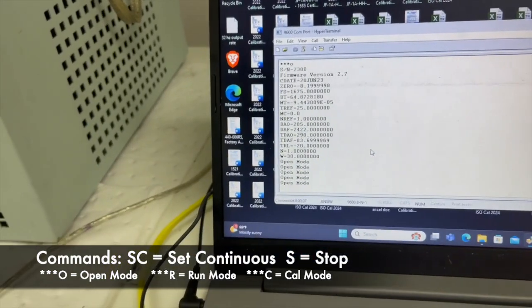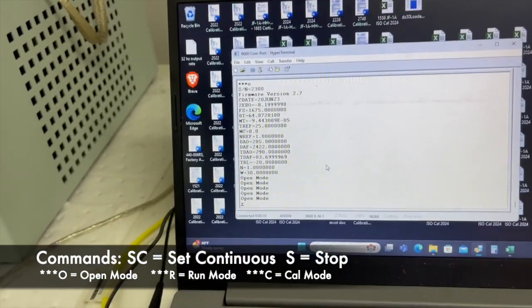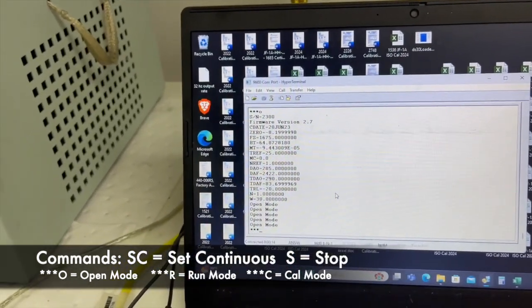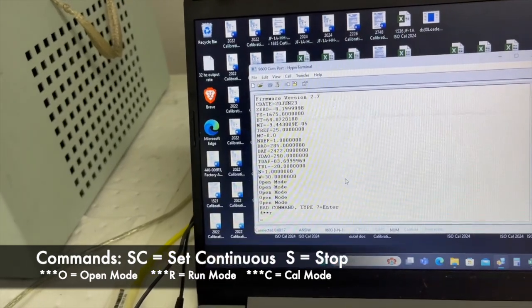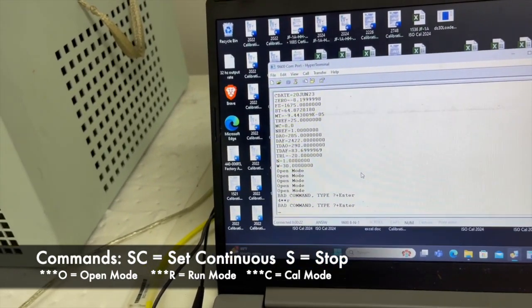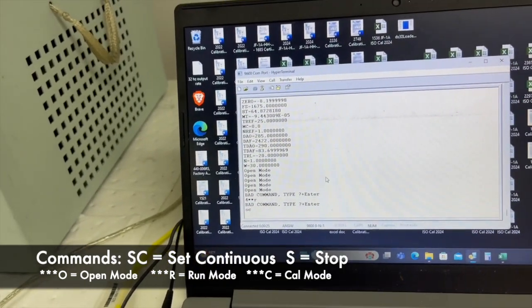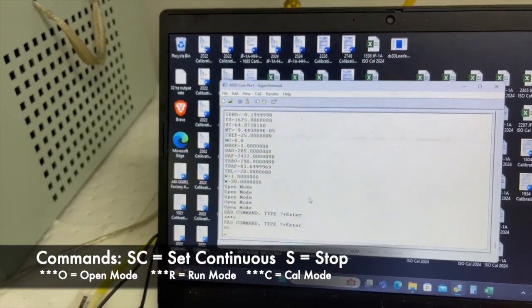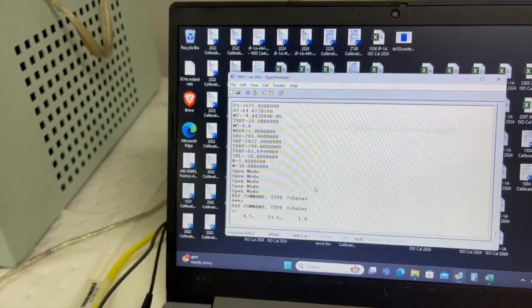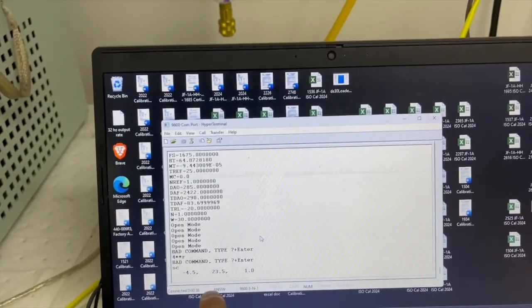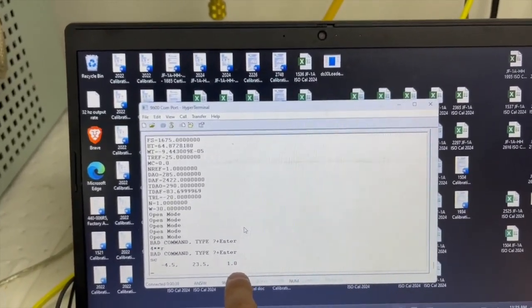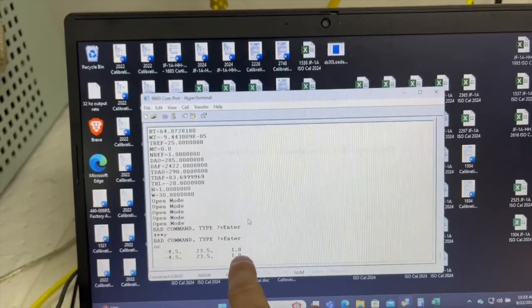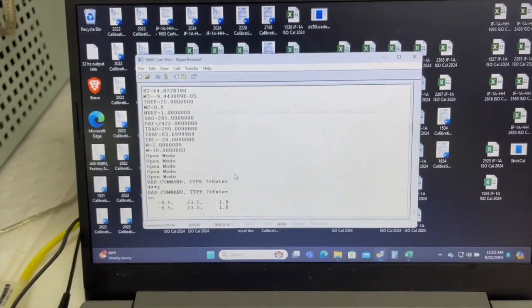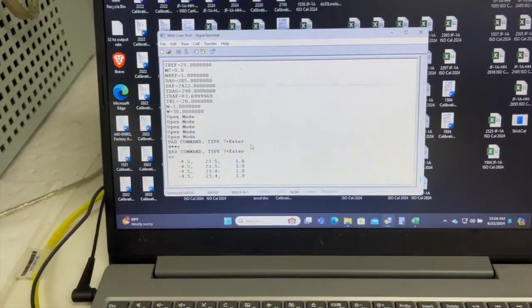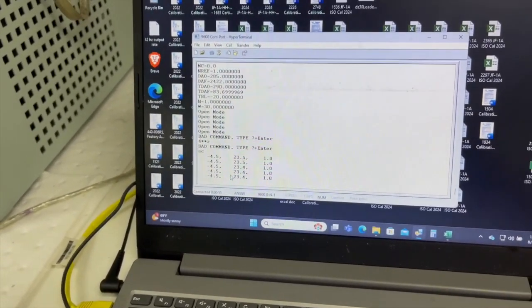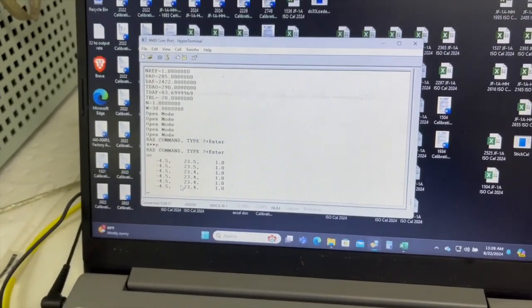If it's in open mode, you can hit, or normally it would pop open in run mode, which is star R. It's already in run mode. Hit SC, it'll start taking data points. And in run mode, it gives you conductivity, temperature, and compensated conductivity. So that's the conductivity when adjusted for the temperature. Which it's in air, so 1.0 is about correct. These sensors generally read a few minus in air, just the way they're calibrated.